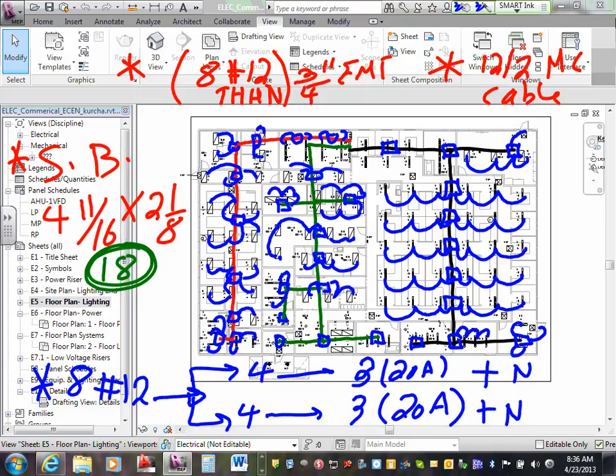This box, based on the box fill, because the inspector will catch you in the box fill. Based on the box fill, guys, this baby can handle 18 conductors. I can bring 18 conductors. You bring 19 conductors, you violated the code. So that's why if you stick with the 8 number 12, that will also take into consideration how many conductors you can bring in the deepest box that you can install, a deep box like this, 18 conductors.